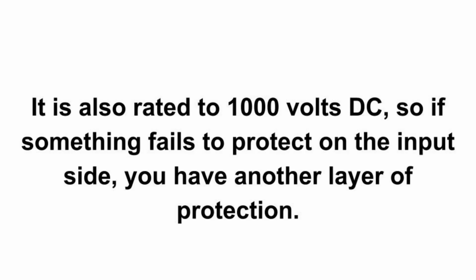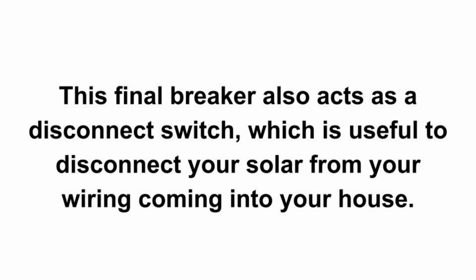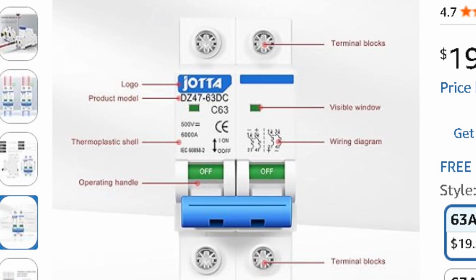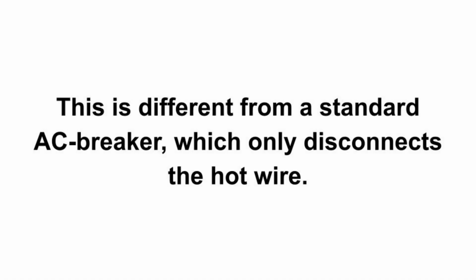It is also rated to 1000 volts DC, so if something fails to protect on the input side, you have another layer of protection. This final breaker also acts as a disconnect switch, which is useful to disconnect your solar from your wiring coming into your house. DC disconnect breakers switch both the positive and negative wires, so there is no connection whatsoever from the disconnect equipment. This is different from a standard AC breaker, which only disconnects the hot wire.